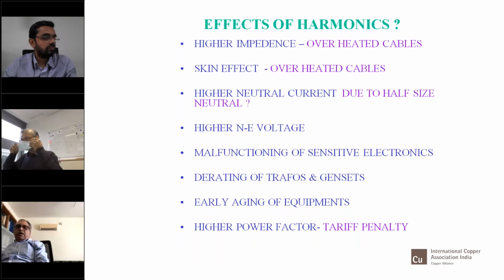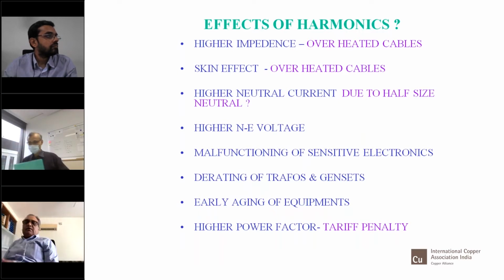Then we have malfunctioning of sensitive electronics because of these kinds of harmonics. We have derating of transformers and generators because of the heating and impedance increase caused in the transformers and gensets. A 1000 kVA transformer can no more be used as 1000 kVA. It will have to be used as a 700 kVA transformer. And the same is with the generator, or even a little more, because generators are still more sensitive to harmonics.